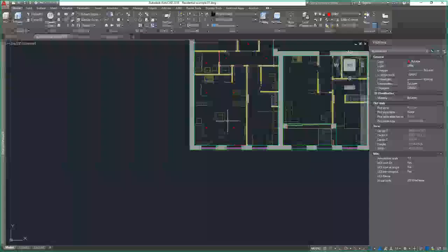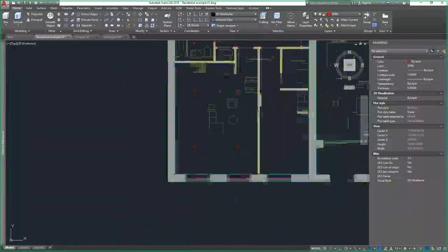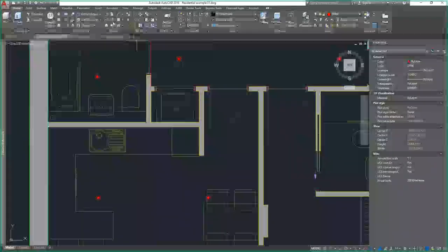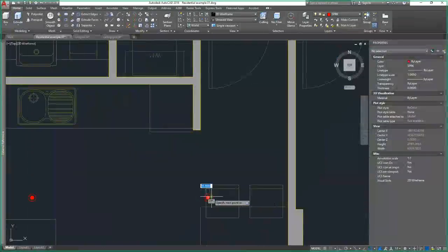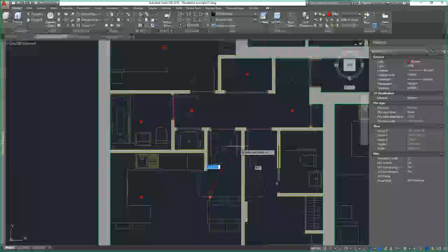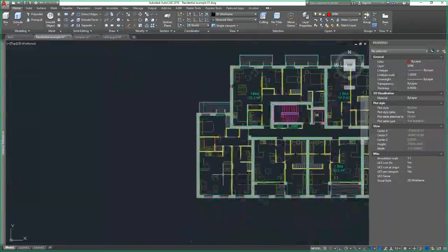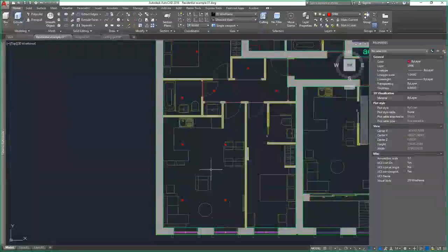However, there's a problem with this design. Maybe you've already noticed what the problem is, and that is, remember, the area by the door. Okay, so let's have a look at that. What is the distance from this head to the door? Well, it's about 2.4. So that's no good because I can only have 2.25. So it means that this area here by the door is not currently protected. So, problem. I'm going to have to put another sprinkler head over here.